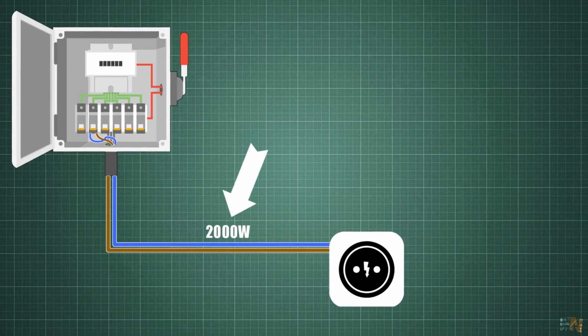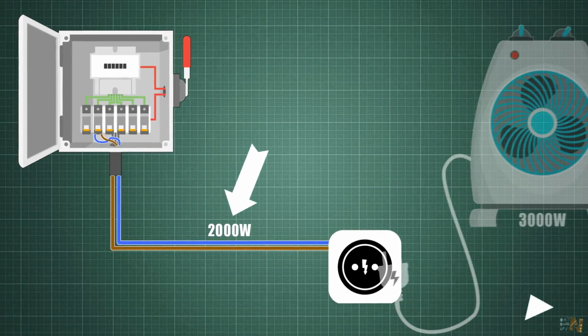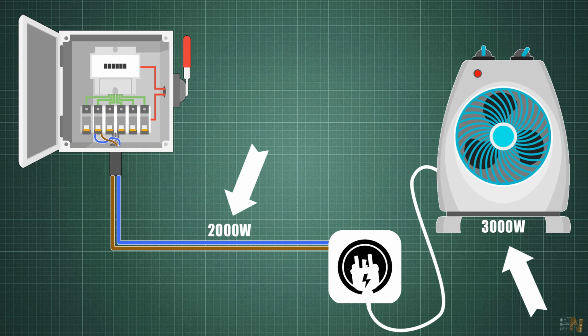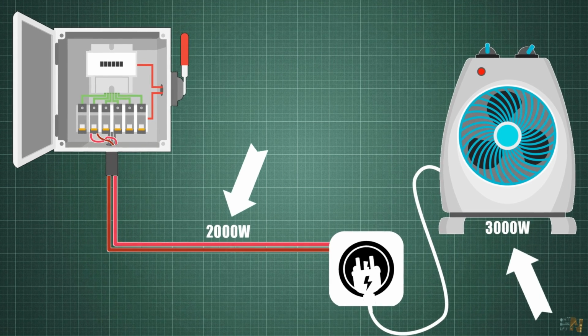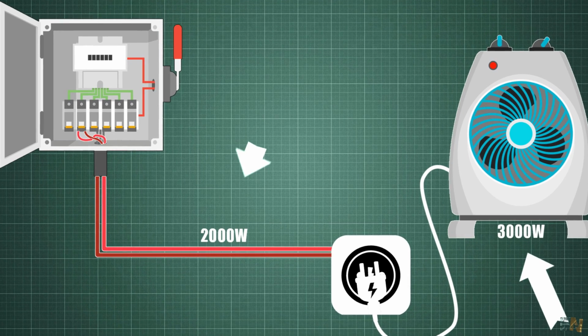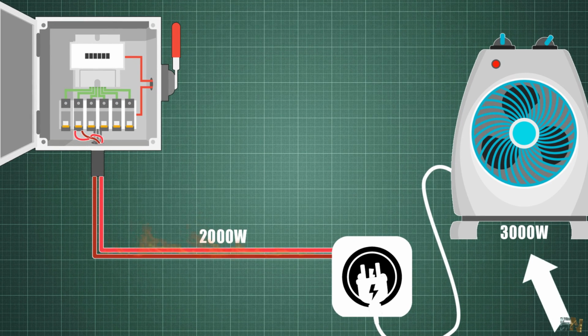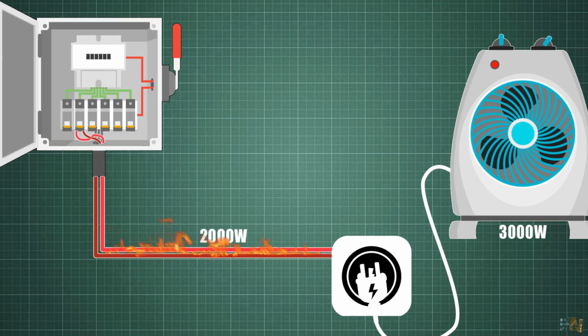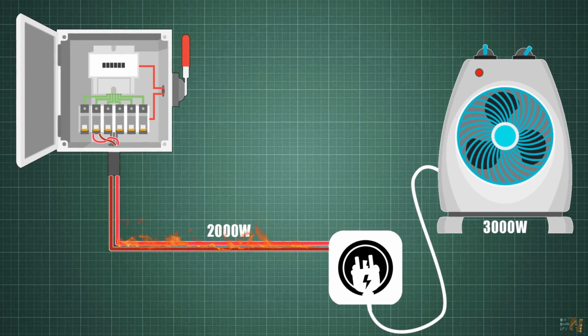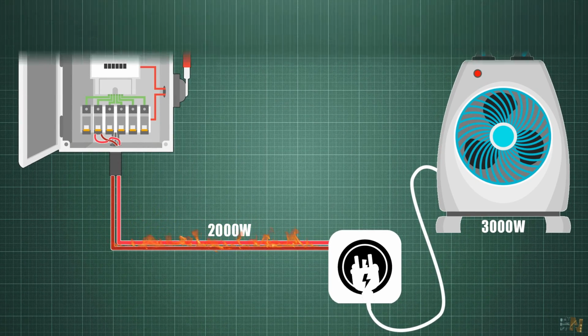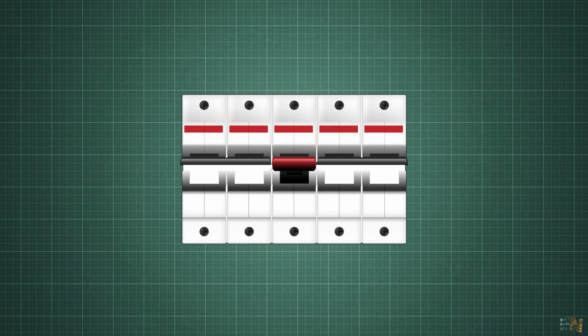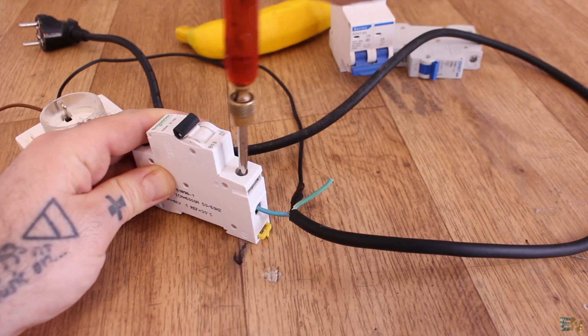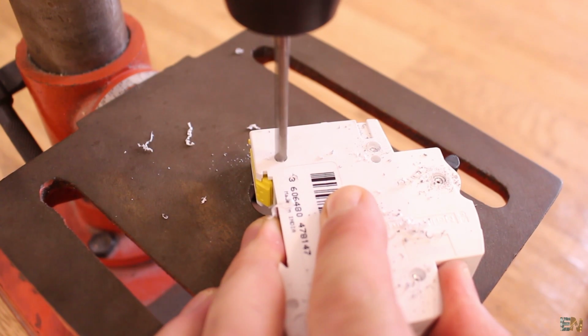If that power limit is overpassed for a long time, let's say instead of 2000 watts we connect a 3000 watts device, the cables could get quite hot, because they are not suited for that power. That power could even melt the wires or create a fire inside of our walls. And of course we don't want that. To prevent that, we use the thermal breaker capabilities of this device. So first we do a test for that, and then we open the MCB and see how it works inside.